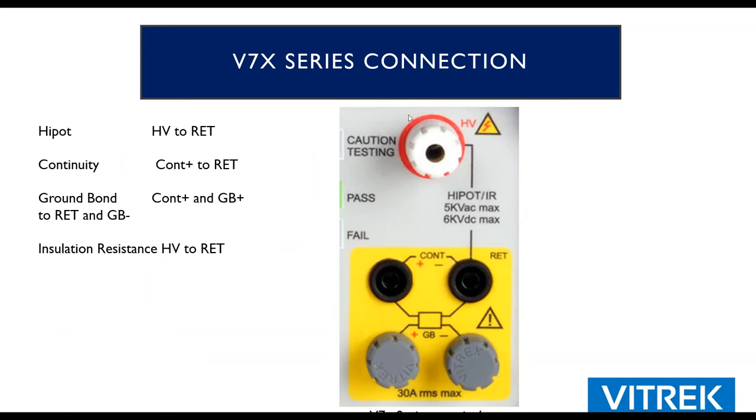A common question is: how do I connect my DUT? A hipot or IR test is always from the high voltage to the return terminal. Continuity is from the return terminal to the continuity source terminal — always a two-wire measurement. Ground bond is a four-wire Kelvin measurement, with the continuity plus and ground bond plus terminals on one side and the return and ground bond minus terminal on the other. The four-wire measurement nulls out any voltage drop in the test leads, which is very important for precise measurements, especially below 100 milliohms.